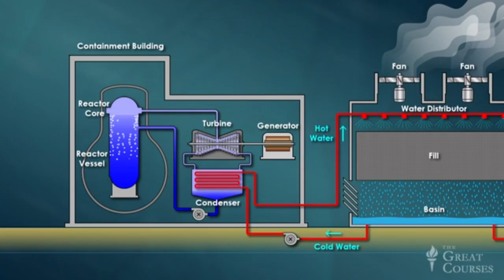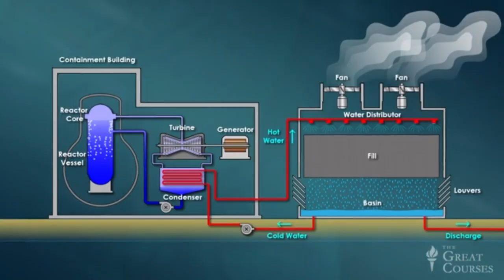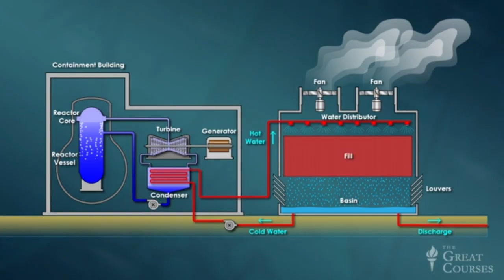In order to cool and condense the steam exhausted from the turbines, a self-contained loop of cooling water is circulated through the condenser. As it removes heat from the steam, this water gets hot and must itself be cooled off before it can be recirculated or returned to the watercourse from which it came. And this is necessary because dumping hot water into a river can harm aquatic life. The hot water is pumped to the top of the cooling tower, distributed around its perimeter, and then allowed to trickle down through an open web of plastic called fill.